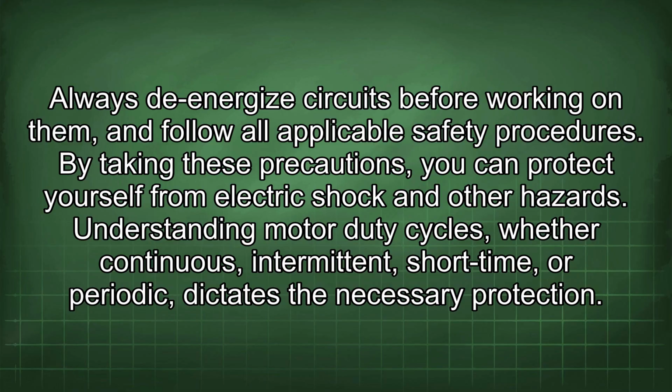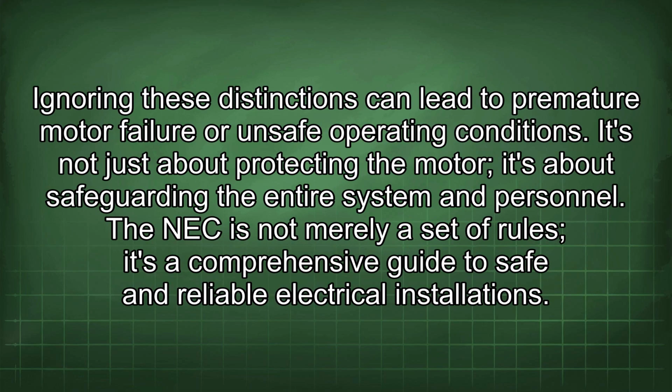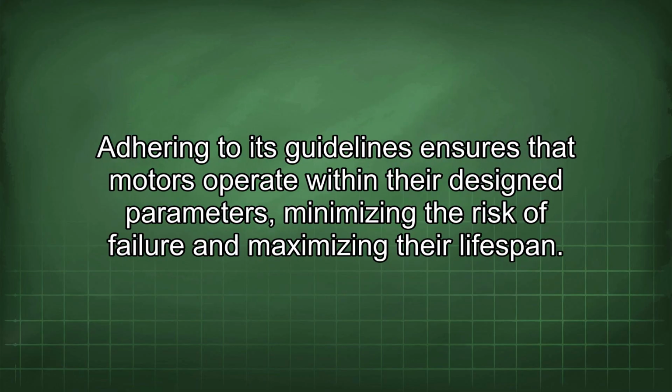Understanding motor duty cycles, whether continuous, intermittent, short time, or periodic, dictates the necessary protection. Ignoring these distinctions can lead to premature motor failure or unsafe operating conditions. It's not just about protecting the motor, it's about safeguarding the entire system and personnel. The NEC is not merely a set of rules, it's a comprehensive guide to safe and reliable electrical installations. Adhering to its guidelines ensures that motors operate within their design parameters, minimizing the risk of failure and maximizing their lifespan.